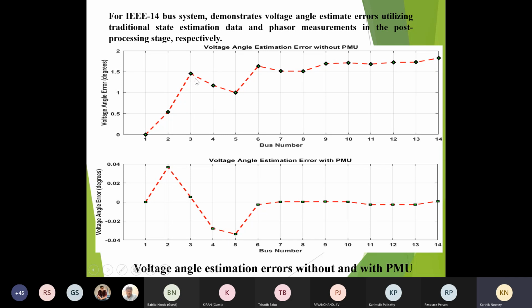PMU is nothing but a device which measures the exact value of voltage. With state estimation you get this much error, but by using PMUs the exact value of the voltage at that particular bus is measured, where that error is decreased by this component. That's what you have to understand from the graph. PMU doesn't actually decrease that particular error; what it does is exactly measure the value.